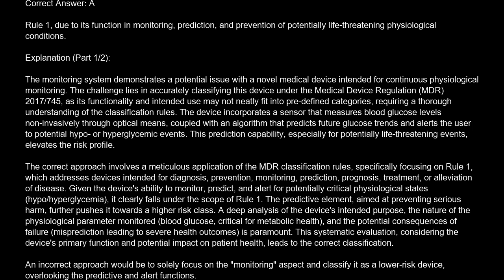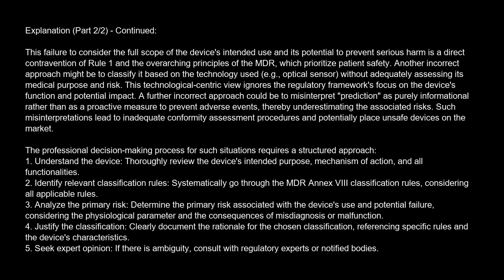An incorrect approach would be to solely focus on the monitoring aspect and classify it as a lower-risk device, overlooking the predictive and alert functions. This failure to consider the full scope of the device's intended use and its potential to prevent serious harm is a direct contravention of Rule 1 and the overarching principles of the MDR, which prioritize patient safety. Another incorrect approach might be to classify it based on the technology used, e.g., optical sensor, without adequately assessing its medical purpose and risk. This technological-centric view ignores the regulatory framework's focus on the device's function and potential impact. A further incorrect approach could be to misinterpret prediction as purely informational rather than as a proactive measure to prevent adverse events, thereby underestimating the associated risks. Such misinterpretations lead to inadequate conformity assessment procedures and potentially place unsafe devices on the market.